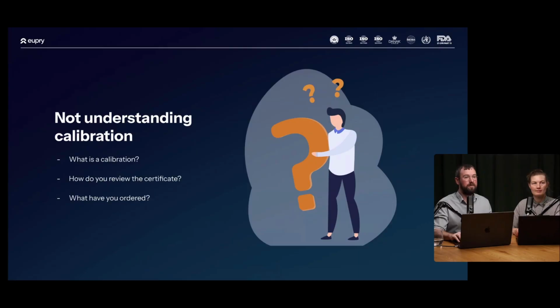Secondly, we have not understanding calibration. We see a lot of findings with customers because calibration has been purchased as an off-the-shelf thing. And it is in most cases, but you need to understand, rudimentarily, what a calibration is, why we do it, and the whole process that we have been through here. What is your process? What is that set of requirements? And what calibration requirements have you set? And that's the certificate we end up with. Because if we don't know what our requirements are, how can we review a certificate? And secondly, how do you actually review a certificate?